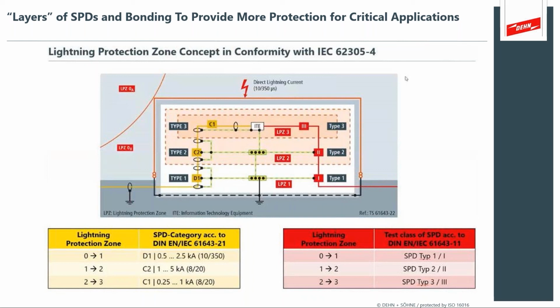In other words, we want the SPDs to really limit that power frequency follow current that comes through the SPD, up to a point where it isn't sensed as an earth leakage or an earth fault. So you don't want to lose the reliability of the circuit every time a surge comes through. You know what I mean? Right. Then we have a question.